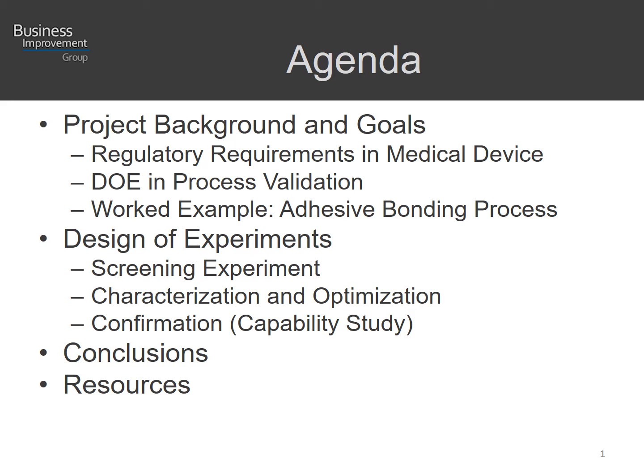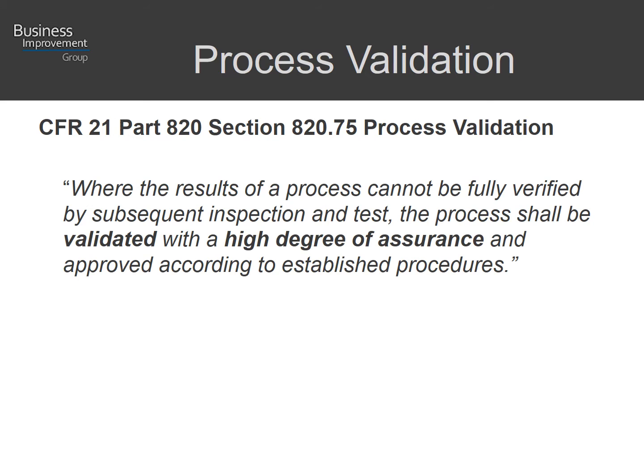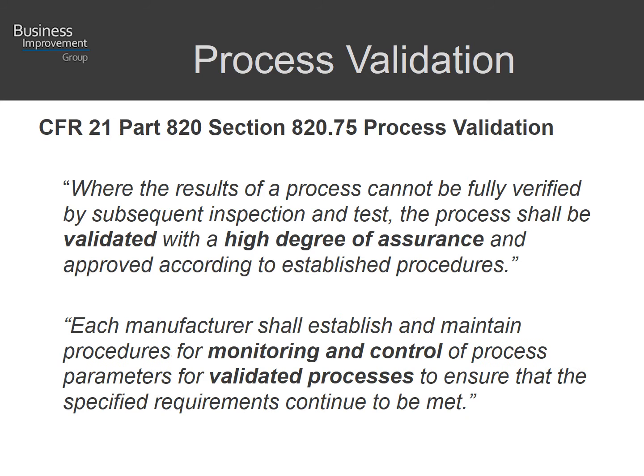We'll then share the conclusions of the worked example and some of the resources we've referred to. Process validation from the FDA is defined as a requirement where the results of a process cannot be fully verified. Processes must be validated with a high degree of assurance to ensure that the process is meeting proper requirements. A monitor and control should be put in place to ensure that validated processes continue to perform to the desired performance.